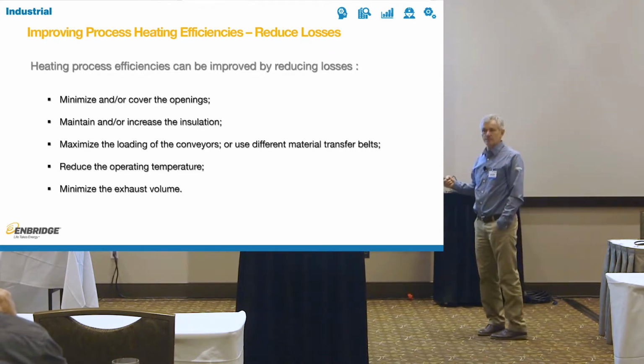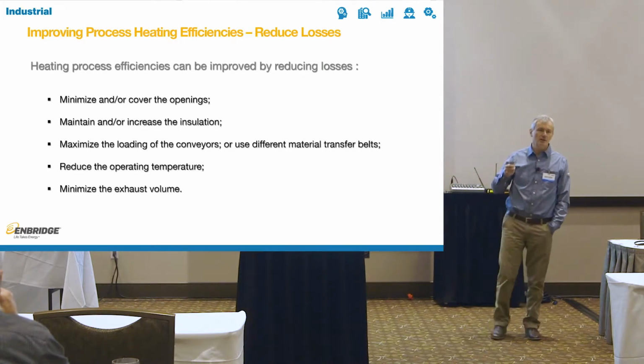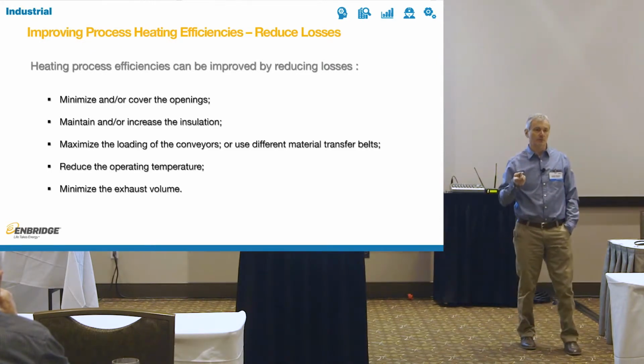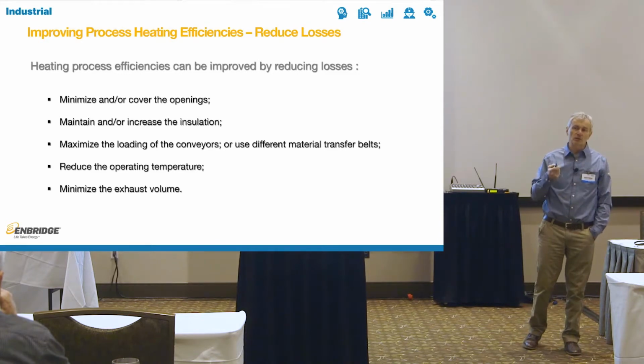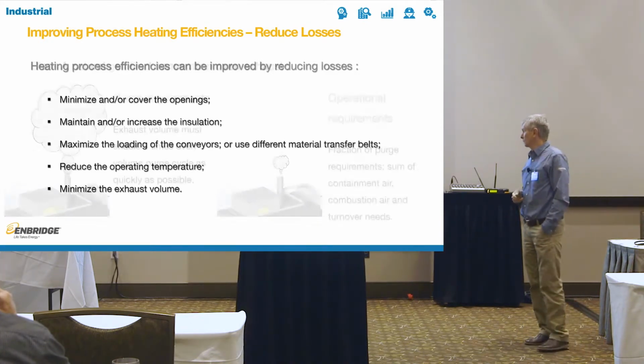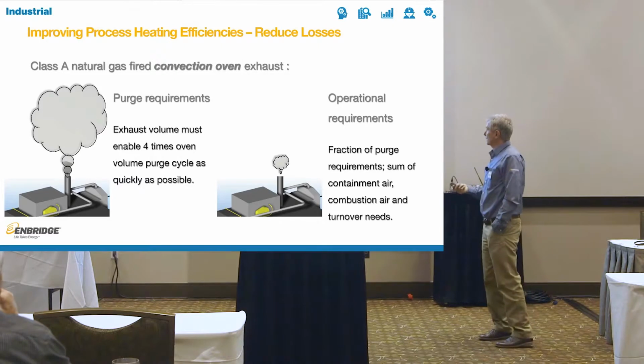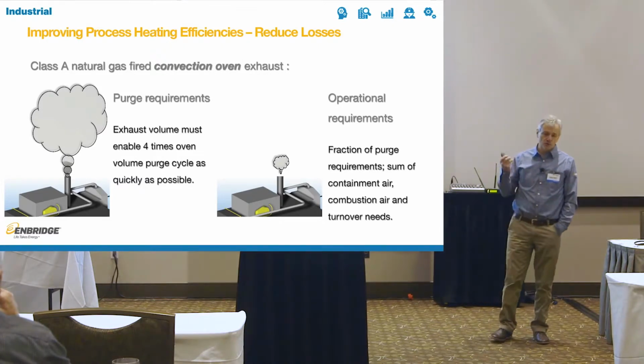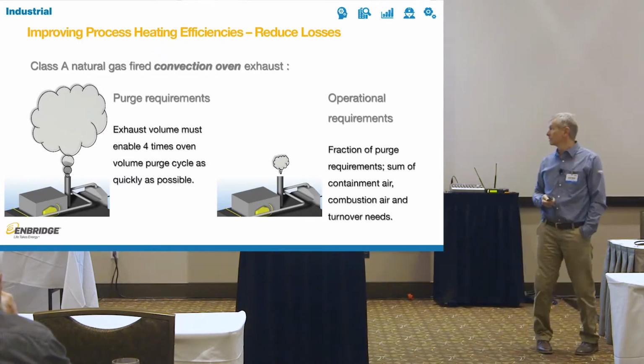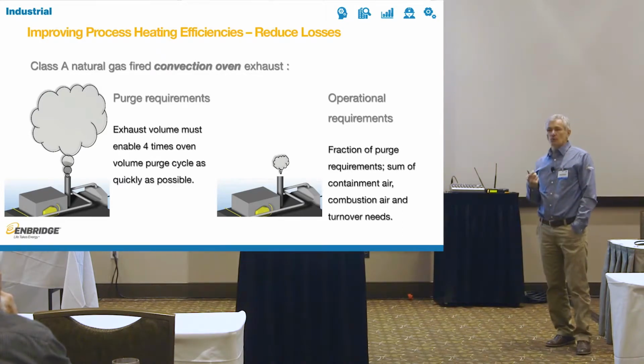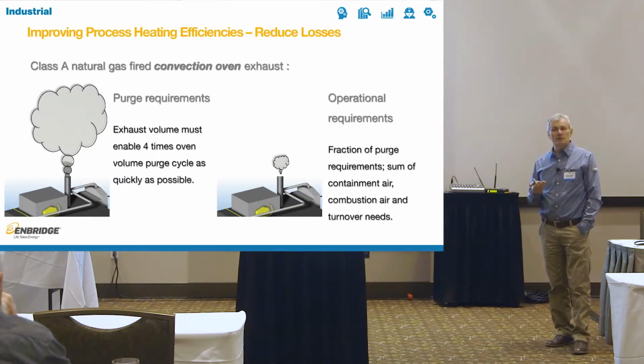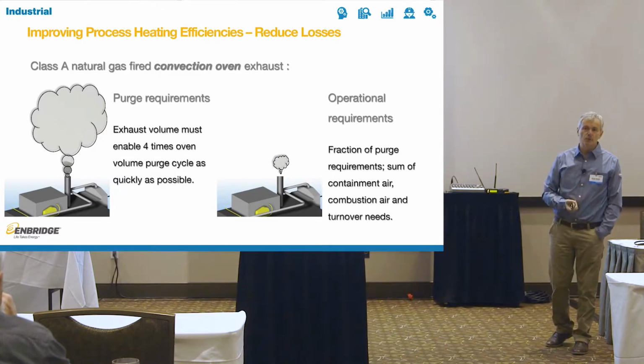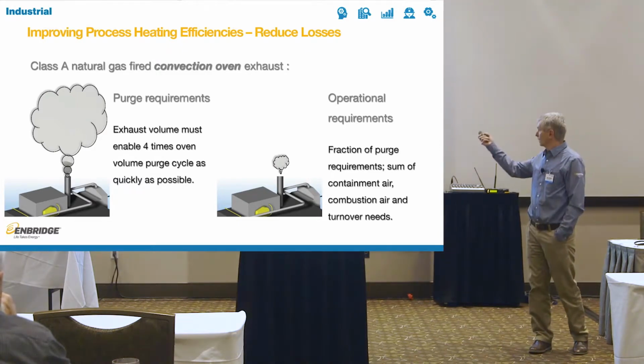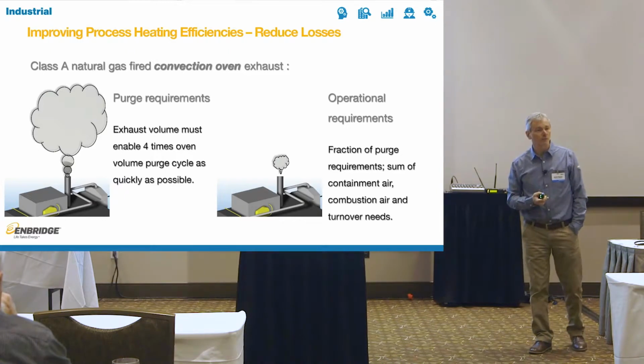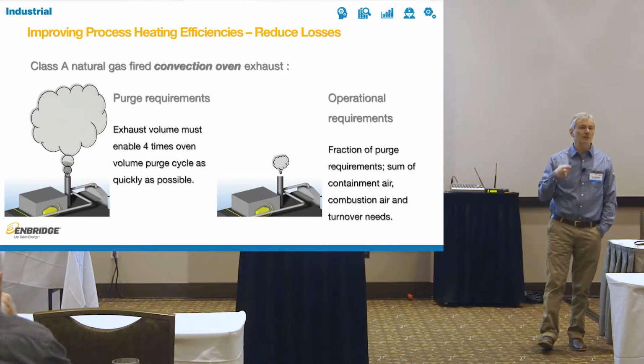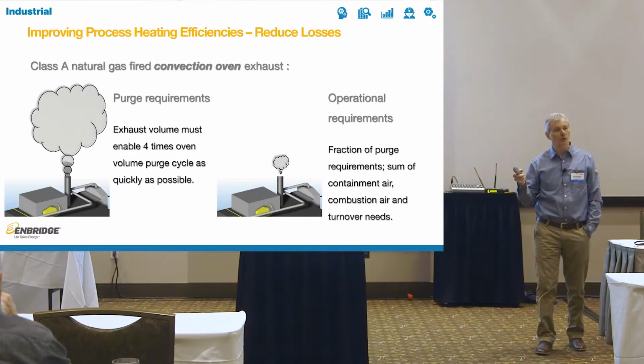Minimize the exhaust volume. This is a big one on finishing lines because exhaust represents a significant part of your losses, and it's a total waste. We'll get to that in a little more detail. For example, a Class A natural gas fired convection oven, which is most of the finishing ovens in our province, will have something called purge requirements, which means that you cannot start the oven. You cannot provide the flame to your burner until you have exhausted 4 times the volume of the oven. So every time you start the oven, you have to exhaust 4 times the volume of the oven out.